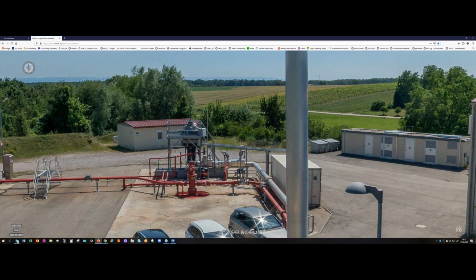Thanks. Do you have a casing problem in the production well before the brine goes to the separation system? No, so far not. But as we are obliged to frequently control the integrity of our well, whenever we have maintenance operations, this will occur next year once the pump is relieved. There will be a very intensive logging program within the production well to control the wall thickness of the casings, the internal diameters, and similar parameters. But actually, we do not have indications that there might be wear of the casing structure within the well.